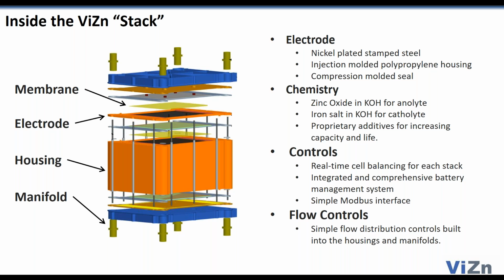The chemistry we run through the stack is zinc oxide and potassium hydroxide for our anolyte, and an iron salt with potassium hydroxide for the catholyte. If the two are mixed, you do lose some performance, but there's no catastrophic reaction or event from mixing—we can cross-contaminate to relatively high levels with negligible impact on performance. We have proprietary additives in the chemistry that really get us our capacity and life in the product.